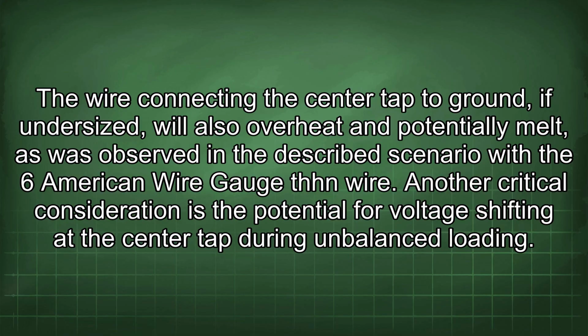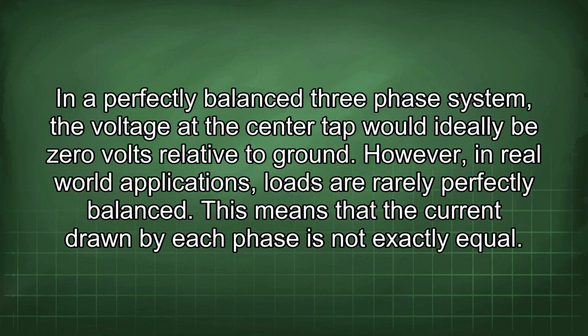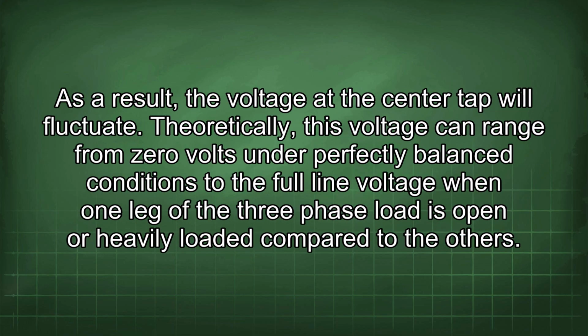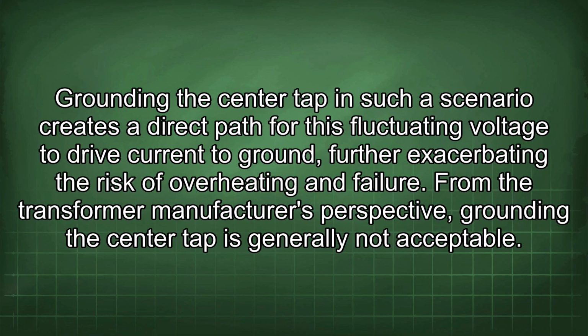Another critical consideration is the potential for voltage shifting at the center tap during unbalanced loading. In a perfectly balanced three-phase system, the voltage at the center tap would ideally be 0 volts relative to ground. However, in real-world applications, loads are rarely perfectly balanced. This means that the current drawn by each phase is not exactly equal. As a result, the voltage at the center tap will fluctuate. Theoretically, this voltage can range from 0 volts under perfectly balanced conditions to the full line voltage when one leg of the three-phase load is open or heavily loaded compared to the others. Grounding the center tap in such a scenario creates a direct path for this fluctuating voltage to drive current to ground, further exacerbating the risk of overheating and failure.